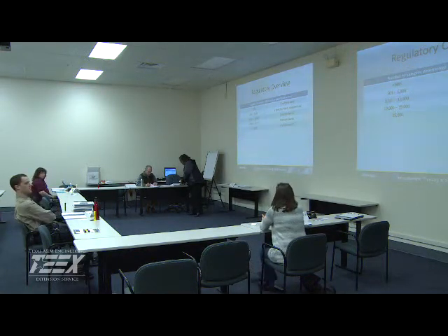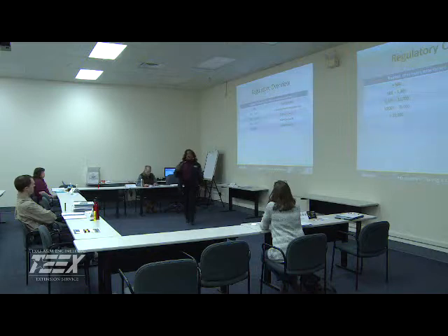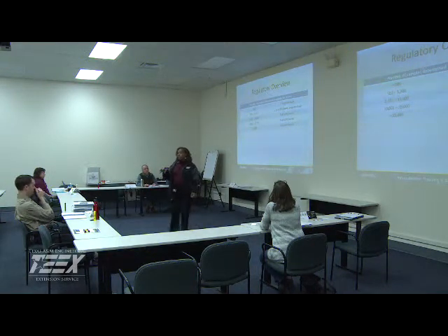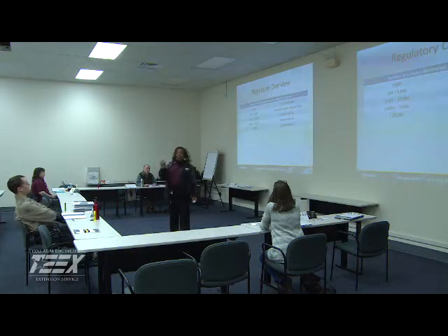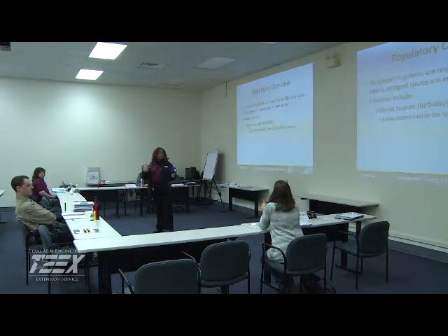They were monitoring routinely every day: chlorine, turbidity. Now with the turbidity, it's going to be a little more, because with filter sources, you're going to run those turbidity readings every 15 minutes on some sources, and on some of your groundwater sources you're looking at every 4 hours. We'll get to that.